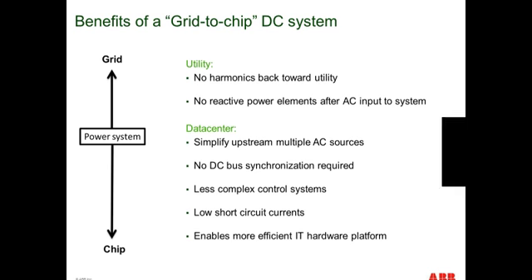At the data center side, you could potentially simplify your multi-source AC design. And rather than having a complicated and expensive parallel generator system, you could look to implement a simple distributed generator system. The DC bus, as Frank mentioned earlier, allows us to parallel multiple DC sources so they're connected simultaneously. Using droop compensation, we can power that critical load depending upon which source is strongest at the time. And less complex controls really do make it easier for operations to manage the systems.